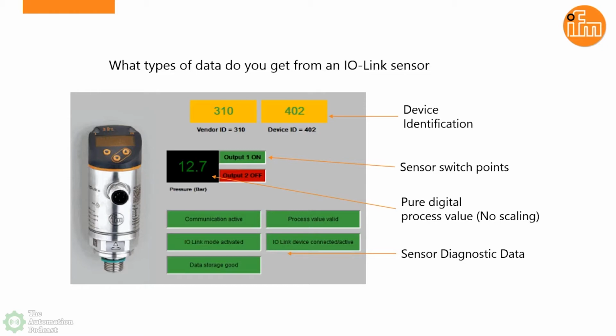You can see here you get the device identification, so you can validate whether a sensor is the correct one that you've placed. Unfortunately, many sensors kind of look alike but might have different ranges, and you might accidentally put a sensor on that isn't correct. But now with IOLink, you can validate that and make sure the end user has placed the correct sensor at the correct location.